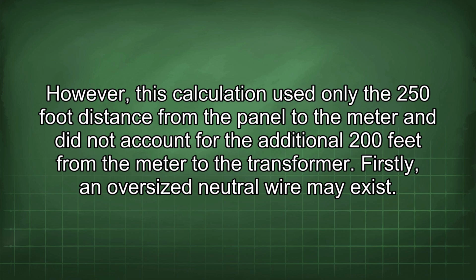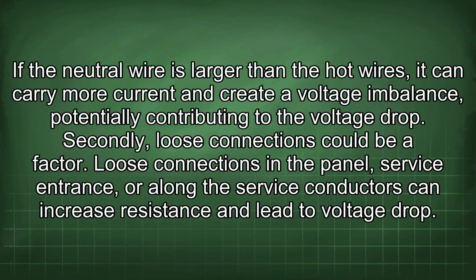Firstly, an oversized neutral wire may exist. If the neutral wire is larger than the hot wires, it can carry more current and create a voltage imbalance, potentially contributing to the voltage drop. Secondly, loose connections could be a factor. Loose connections in the panel, service entrance, or along the service conductors can increase resistance and lead to voltage drop.